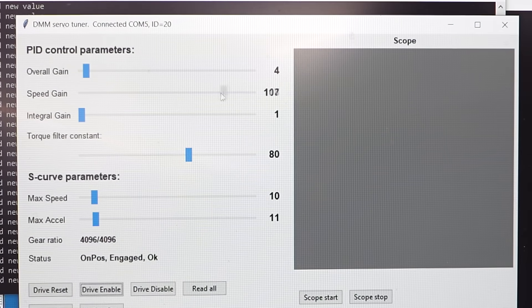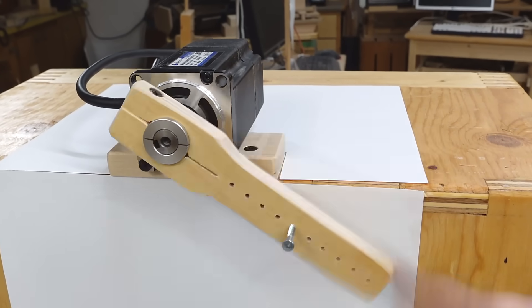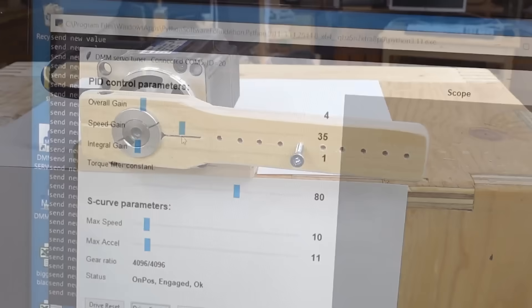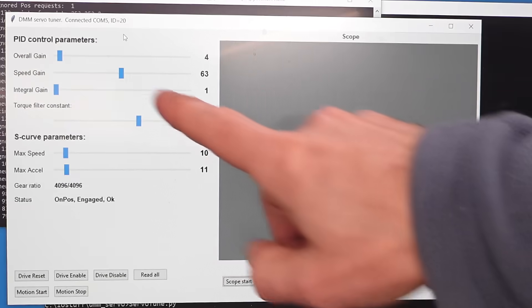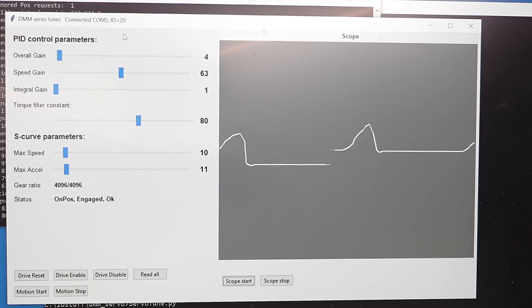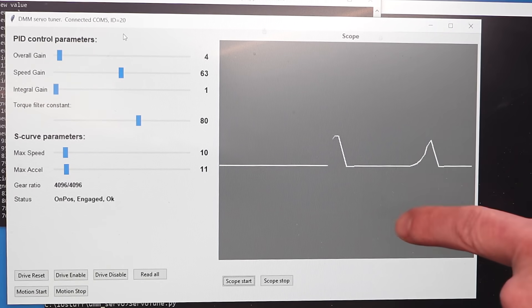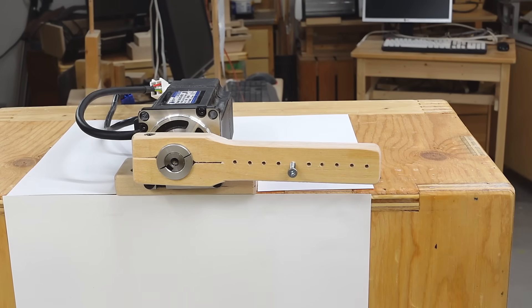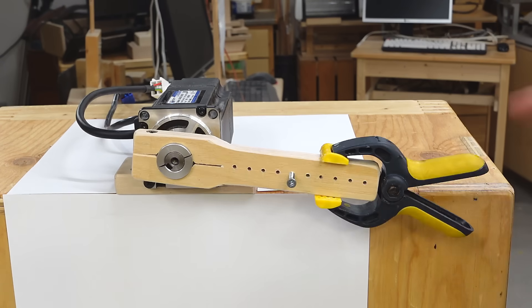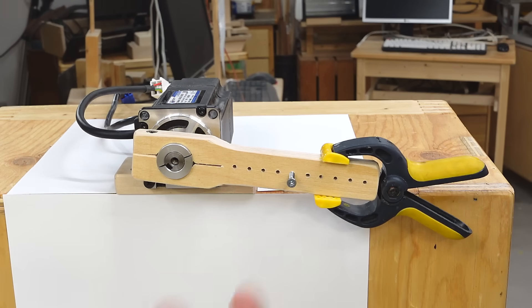Reducing the speed gain (the differential term) a little makes it much less sluggish while still not overshooting. Reducing it more and we can see it overshoots a little. Tweaking it to 63 for the speed gain, we get just a tiny bit of overshoot — and sometimes a little overshoot is acceptable because eliminating it entirely usually makes the motor sluggish. The differential term is all about avoiding overshoot and avoiding oscillations. Note that if I add more inertia with a clamp, I actually need a different speed gain — like a heavily loaded truck that needs to hit the brakes sooner and harder.